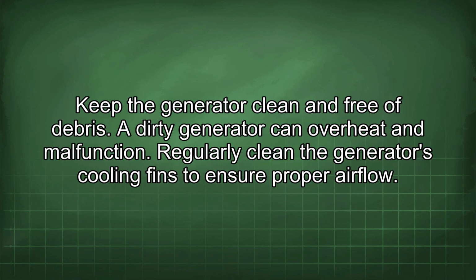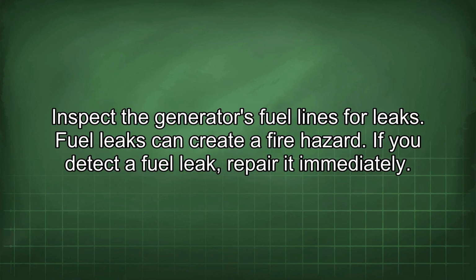Keep the generator clean and free of debris. A dirty generator can overheat and malfunction. Regularly clean the generator's cooling fins to ensure proper airflow. Inspect the generator's fuel lines for leaks. Fuel leaks can create a fire hazard. If you detect a fuel leak, repair it immediately.